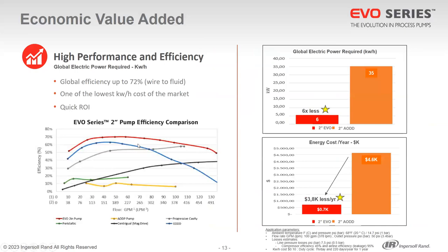I want to go to our next economic value added benefit associated to this new technology. In the graphic below, you can see our features associated to high performance and efficiency. This technology allows us to reach a global efficiency up to 72%. This is global power electric requirement — wire to fluid — meaning efficiency tied to the whole system, not only a specific component like the electric motor. This gives one of the lowest kilowatt costs in the market, as shown here in the graph.